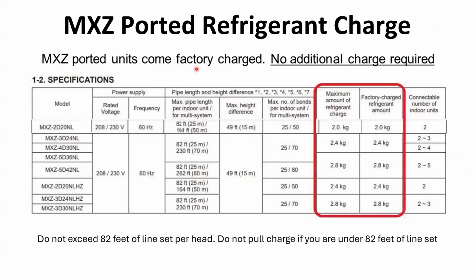On the ported units, the units come factory charged for the full piping amount, so no additional charge is required on certain models. I wouldn't say all the models, so you're going to have to check. But this is what the specifications look like. Here's our max: the MXZ2D Delta 20. The max piping length is 164 feet, and this unit is charged for 164 feet. And so on. These models down here are good for 230, 262, etc. So that's how you read that chart.